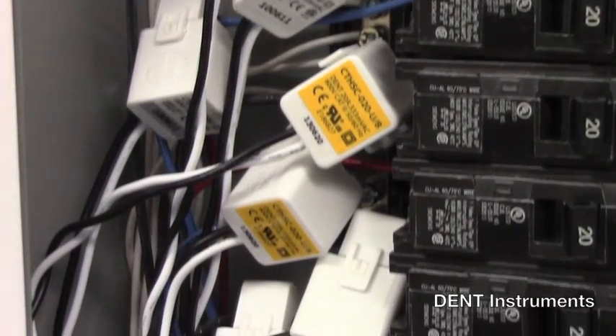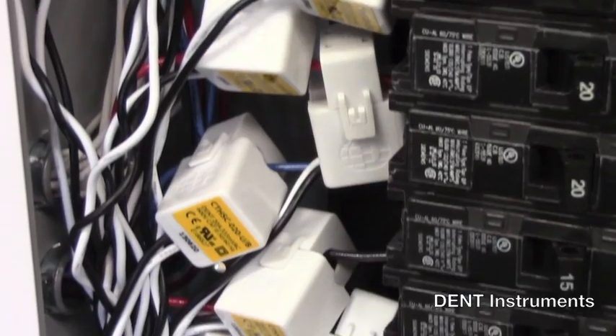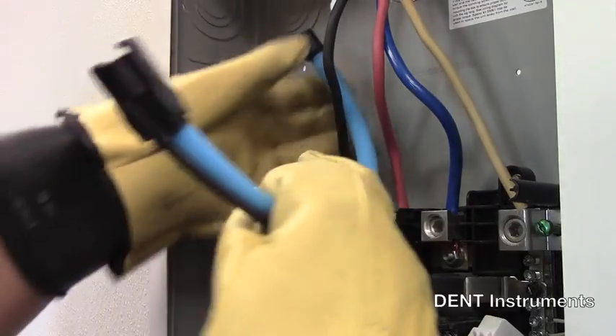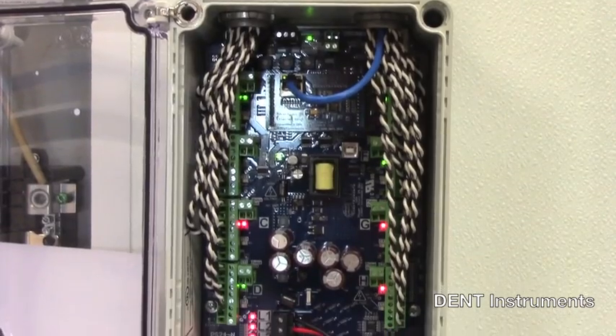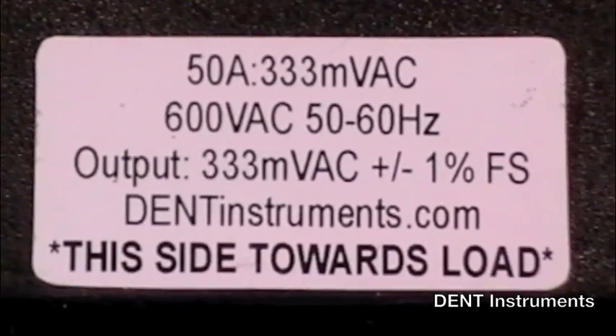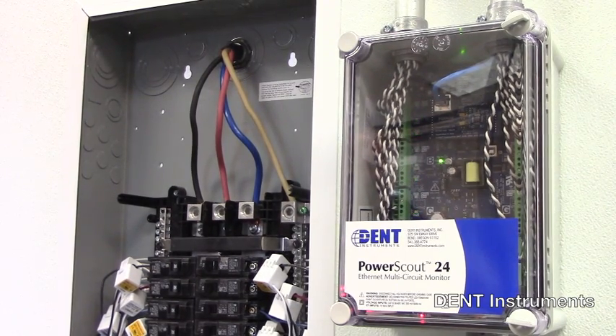The PowerScout 24 can be equipped with any combination of DENT internally shunted, split core, or Rogowski coil current transformers. It is infinitely configurable due to the fact that there are essentially no restrictions in mixing and matching CTs on any of the 24 available inputs. All DENT CTs have a millivolt output, so they are much safer to work with than conventional 5 amp output CTs.